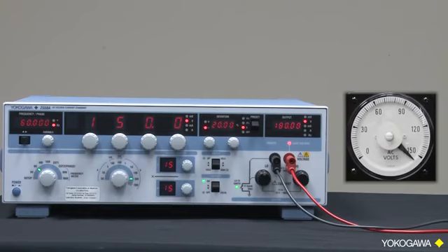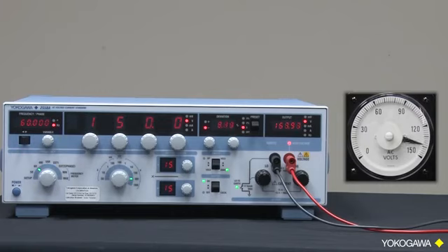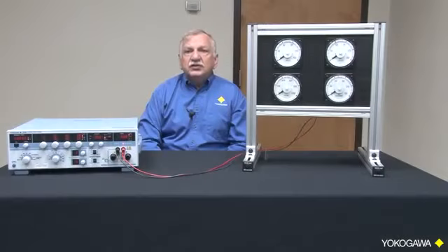Next, I will press the sweep button again to reverse the process, and the pointer should smoothly transition off the pointer stop and continue to smoothly sweep all the way down to 0. Since the 2558A does the sweeping automatically, the operator can keep an eye on the movement of the pointer to ensure that it has no rough spots that could cause it to hang up in normal operation. This could not be done with any consistency if the sweep was done manually.